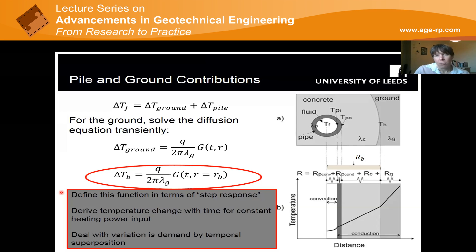So I'm mainly going to talk about this G function, how temperature changes with time for a constant application of thermal load. There are a number of traditional simple models used for this, applied routinely in the design of other ground heat exchangers like boreholes. The most common is the infinite line source, or ILS, where you assume your heat exchanger, your pile, is infinitely long and infinitely thin, which we know it's not, but we'll see it's actually a surprisingly good assumption.